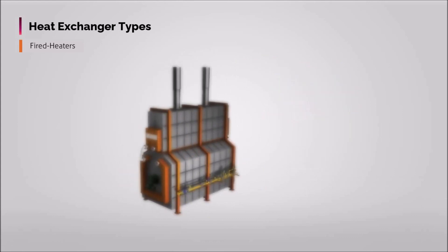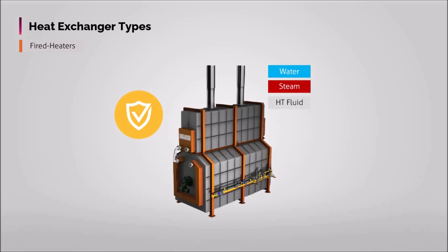Those tubes directly absorb much of the heat from the flame through radiation, and there is also convection from the air between the tubes and the flame, producing an additional amount of heat. Heaters are not common in most field installations but are more commonly used in plant situations where operators routinely maintain and inspect the equipment for safety reasons. Heaters are most often used to heat a heat medium system — water, steam, or heat transfer fluid — rather than to heat the gas or oil stream directly.